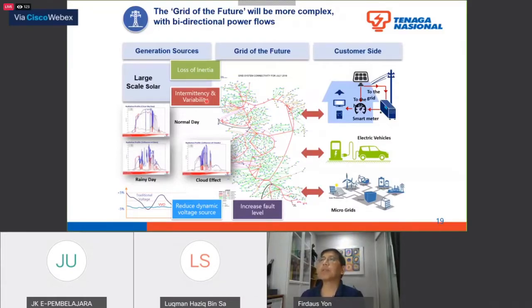There are ways to handle it. So then the other problem is about loss of inertia. Our PV plants are essentially static. They don't move, they don't have any moving parts, so basically they don't have any inertia at all. This is a concern because when we have a fault in the system, PV plants, if they don't have inertial control or inertial help, they will facilitate the collapse of the system, because once you replace a high inertia generation source with a source that has no inertia, you are actually weakening the system.